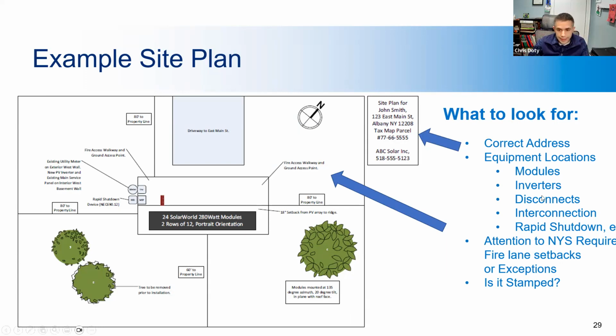That's super important. And it has kind of locations of modules, which will be right here, the inverter, the disconnect, the meter, the interconnect, rapid shutdown initiation device, which you can see right here. So you want to know where those things are going to be located when you go out to the site and you can actually inspect the system. It also has the location of rooftop access and ventilation. It has the location of the utility meter, as I said, the distance to the property line, and like I said, you want to make sure it's stamped by the professional.